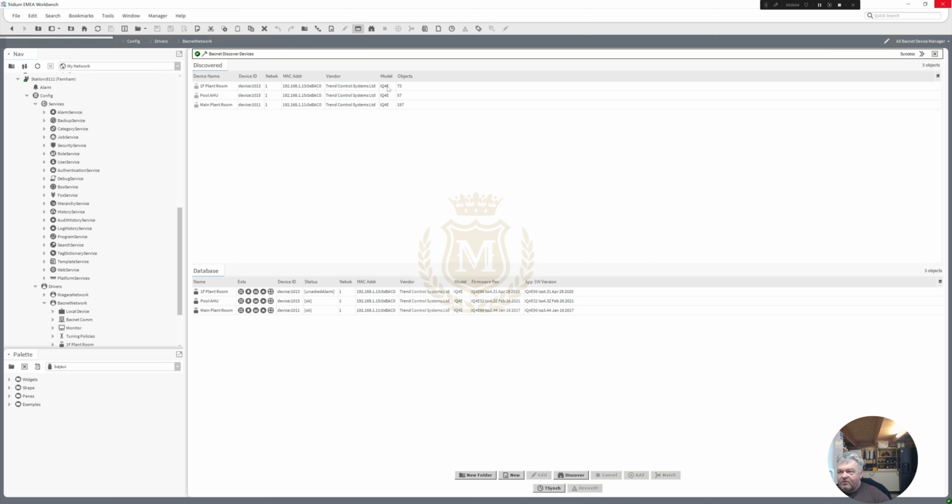So this is a new station that's been set up on site, and it's again talking BACnet to these three IQ3, I presume, controllers. Oh no, they're IQ4Es. So we're talking BACnet to IQ4 controllers. And I've just gone into this. This is what was set up by the site engineer, and I'm now going to go through all these points to make before I send them to the cloud, to add histories to them, alarms to them, and make sure that there's no special characters.